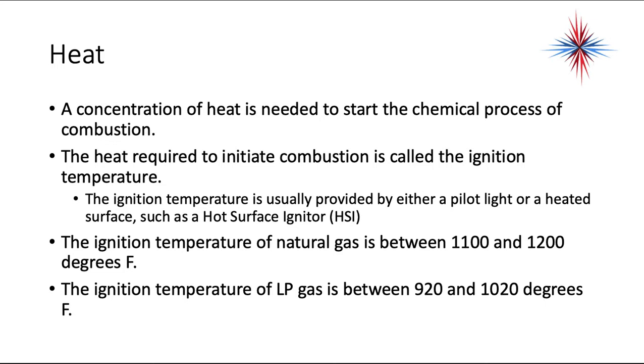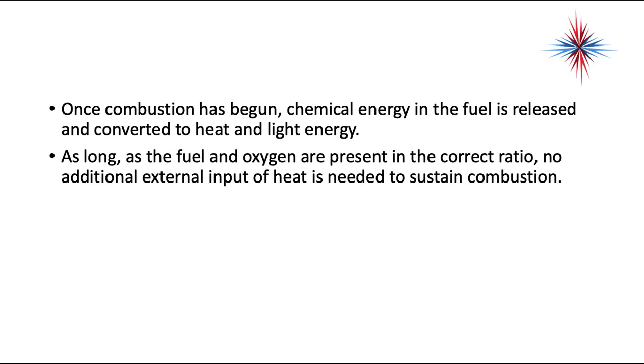A concentration of heat is needed to start the chemical process of combustion. The heat required to initiate combustion is called the ignition temperature, usually provided by a pilot light, a heated surface such as a hot surface igniter, or spark ignition. The ignition temperature of natural gas is between 1,100 and 1,200 degrees Fahrenheit. The ignition temperature of LP gas is between 920 and 1,020 degrees Fahrenheit. Once combustion has begun, chemical energy in the fuel is released and converted to heat and light energy. As long as fuel and oxygen are present in the correct ratio, no additional external heat input is needed to sustain combustion.